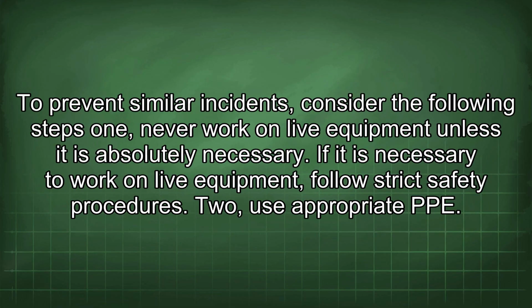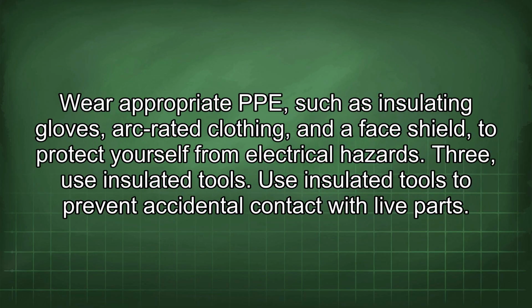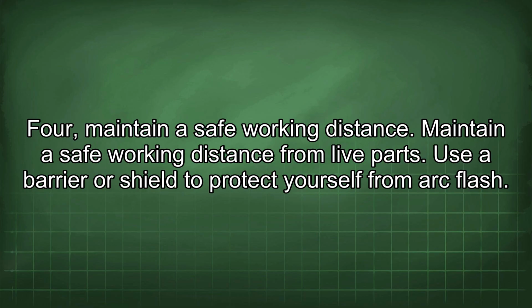To prevent similar incidents, consider the following steps. 1. Never work on live equipment unless it is absolutely necessary. If it is necessary to work on live equipment, follow strict safety procedures. 2. Use appropriate PPE. Wear appropriate PPE such as insulating gloves, arc-rated clothing, and a face shield to protect yourself from electrical hazards. 3. Use insulated tools. Use insulated tools to prevent accidental contact with live parts. 4. Maintain a safe working distance. Maintain a safe working distance from live parts. Use a barrier or shield to protect yourself from arc flash.